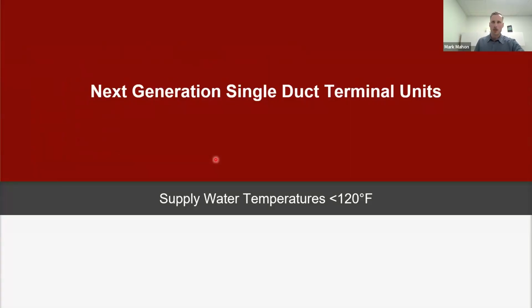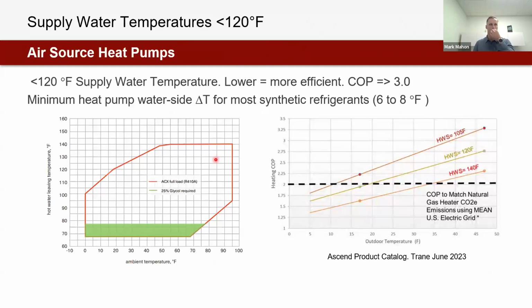And lower supply water temperatures, of course, can be from that air source heat pump or water source heat pump or ground source heat pump. It also can just be from wanting to run a boiler at a lower hot water supply temperature to get even lower return water temperatures to get even higher boiler coefficients of performance. If we want a 98% efficient boiler, we need to return a 60-degree temperature to that boiler.